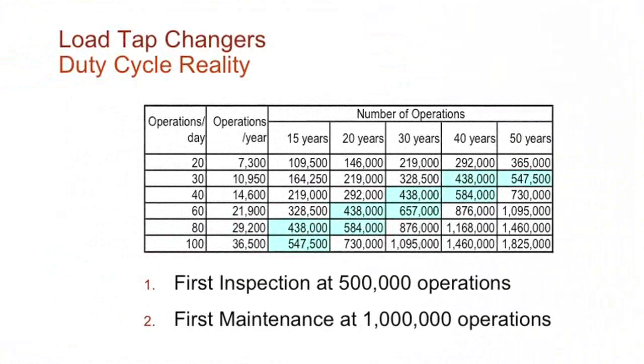There's no electrical, mechanical devices that we use for the timing, unlike the cam switches and everything that are used on a lot of tap changers. The TLMS does all that for us. This just shows you the duty cycle, the number of operations per day, per year, just to give you kind of a chart of how long it would take before you'd actually need to do an inspection on this LTC. You can see it can be as short as 15 years, which is not really that short, but up to 50 years, depending on the number of operations or application you have.